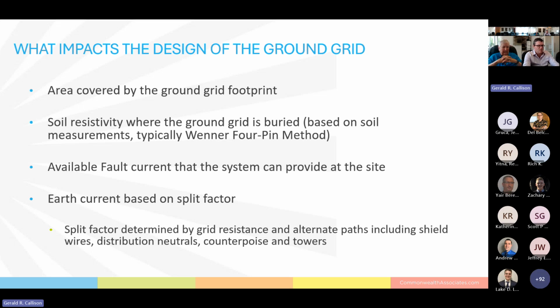Another factor is how much fault current the system can provide at that site. Based on where it's connected in the power system, how much ground fault current is that power system capable of delivering to the point where the ground grid is located? Another important factor in the design of a ground grid is split factor, and I'll show you some pictures in a few slides. Split factor is determined based on the resistance of the grid and the amount of paths leaving the station, such as shield wires and transmission towers, distribution neutrals and distribution towers, counterpoise towers, things like that.